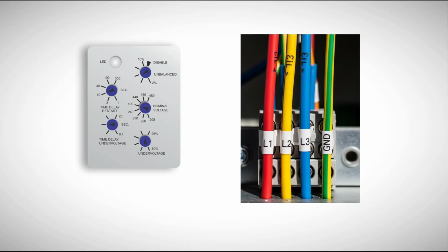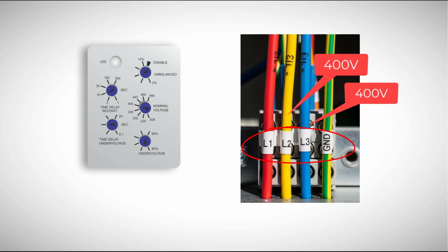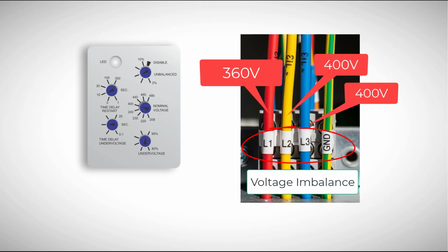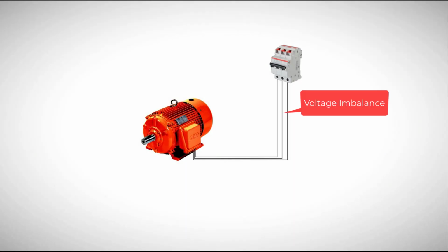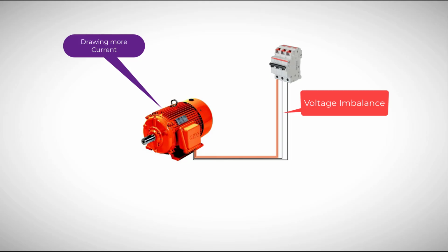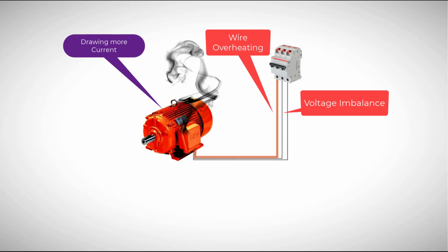In a three-phase system, all three voltages should be nearly equal. When one phase drops, let's say two phases are at 400 volts and one drops to 360 volts, you now have what's called a voltage imbalance. This imbalance might look small, but in reality, it has a huge effect on motors. The motor will try to compensate by drawing more current in the weaker phase. This causes overheating in the windings. Insulation starts to break down, and if not stopped, it can lead to complete motor failure.